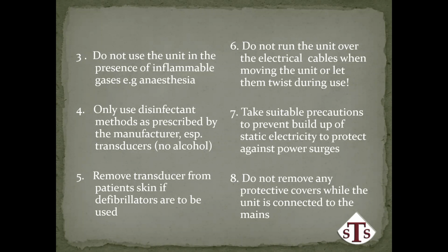Removing the transducer if they're defibrillating is a basic common sense. The next one, not so much. When you move the machine, or if somebody moves it for you, or it has to be taken to a ward to do a portable, just be careful of not running over the electrical cables or the cable linked to the transducer. If any of the wires inside those cables break, then you're going to render your transducer not necessarily completely inoperable, but most certainly not working to its full potential.